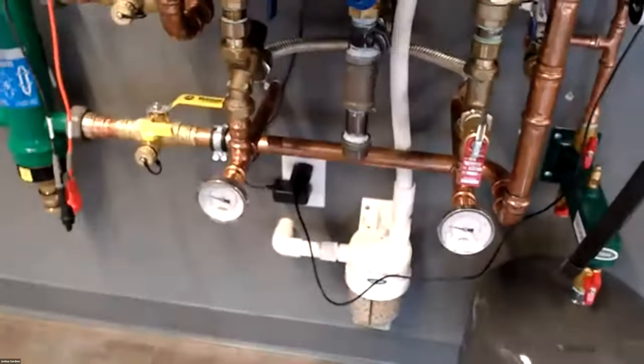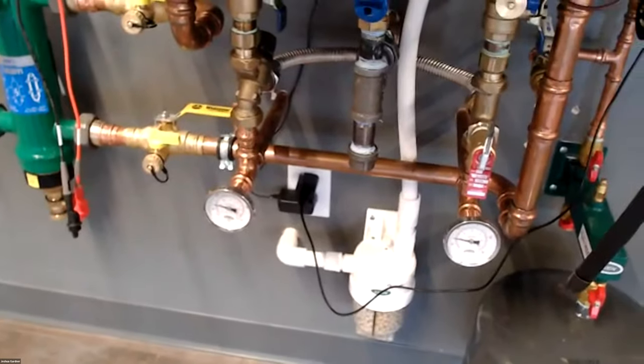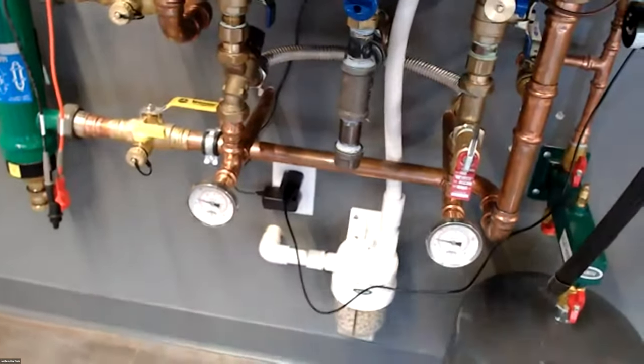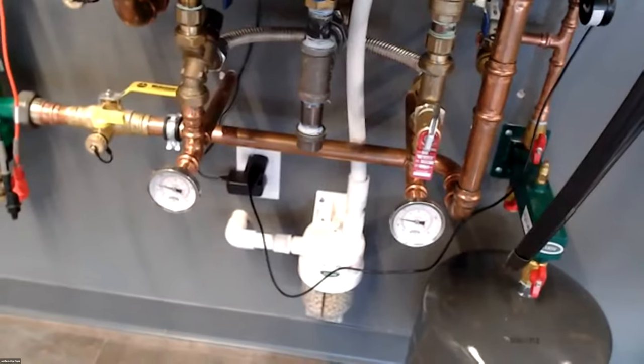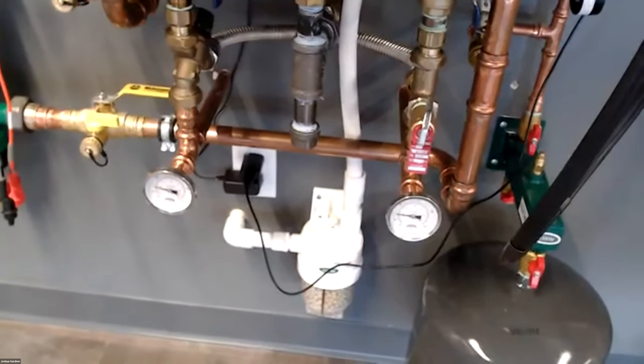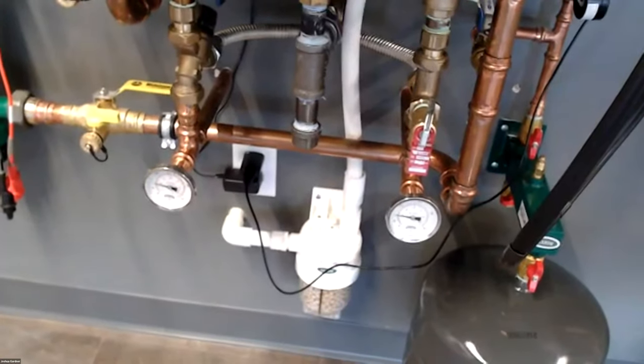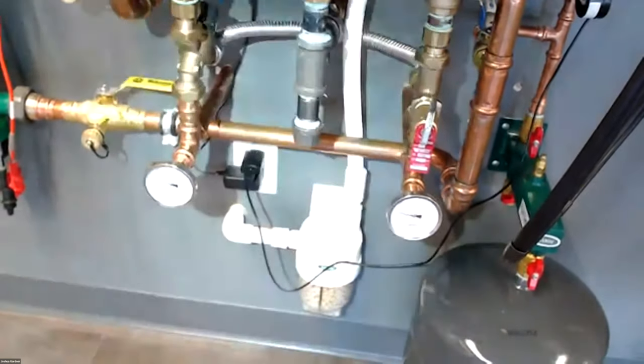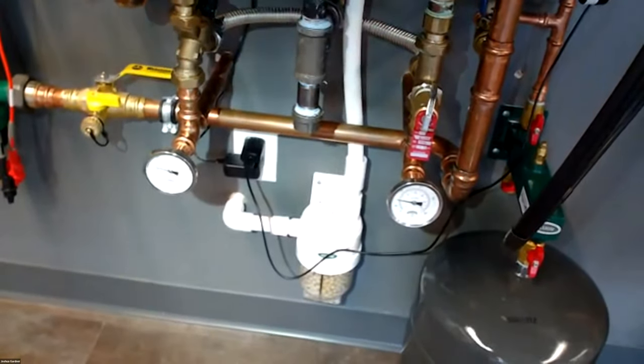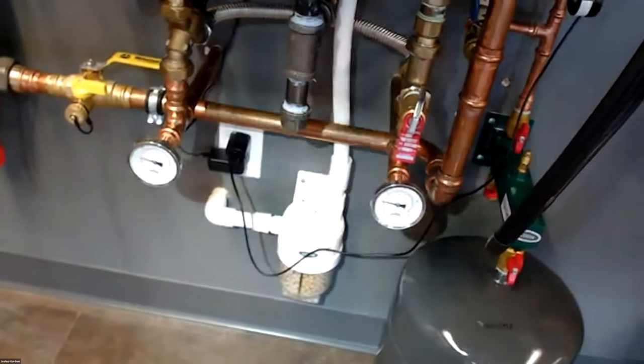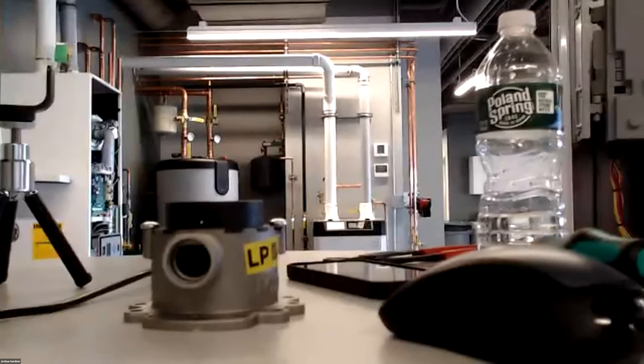So some guys just like dumping this in septic tanks. Yeah, the tank is concrete or poly, which probably won't affect it too much, but it will affect, if there's enough, the leach field, and it will kill the good bacteria in that tank. So make sure even on septic systems, you're using a condensate neutralizer, and that the pellets are changed out every year and serviced, and that your trap is cleaned as well too. Then while we're on that condensate trap, take a look at it, because this is a call I get once in a while.